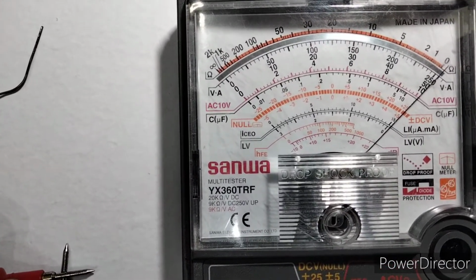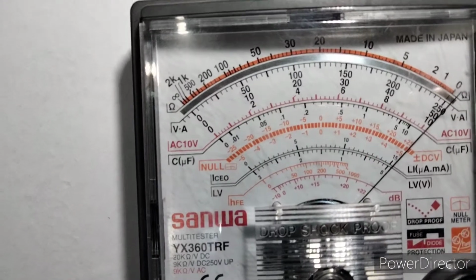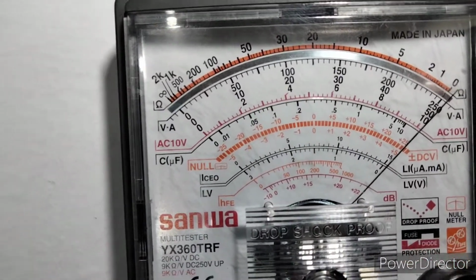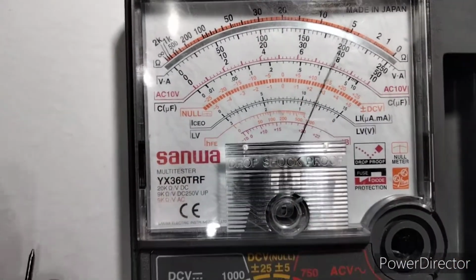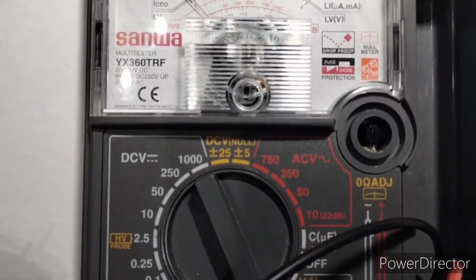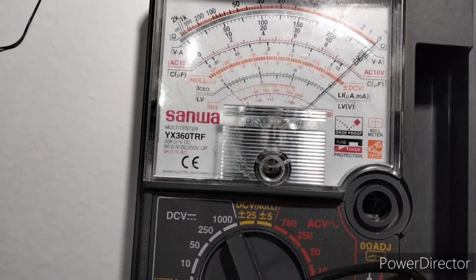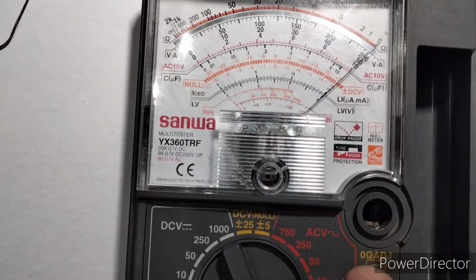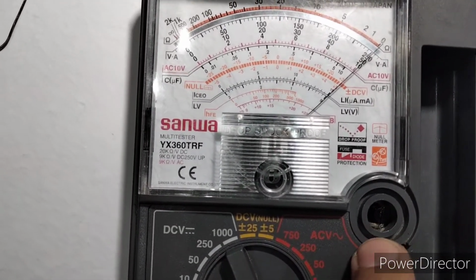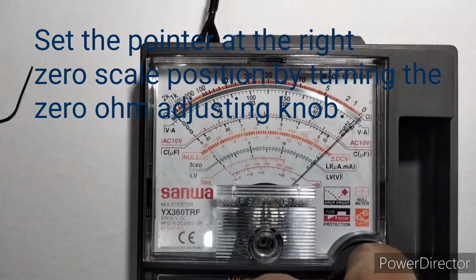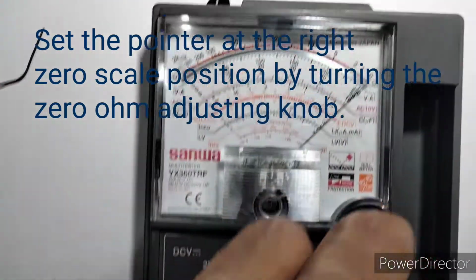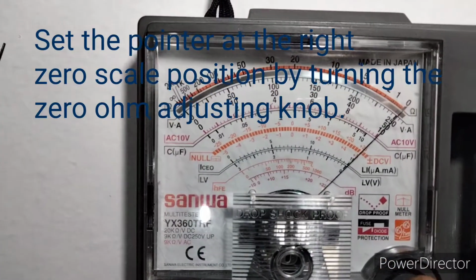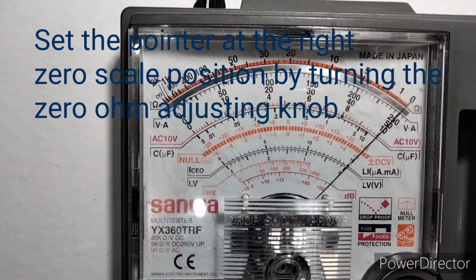So if the pointer is not resting at 0 at the upper scale, you are going to adjust the 0 ohm adjusting knob. The 0 ohm adjusting knob is found here. Unfortunately, we have also lost the knob. So instead, we will just be turning this one. Just move it slowly. Now the pointer is resting at 0.